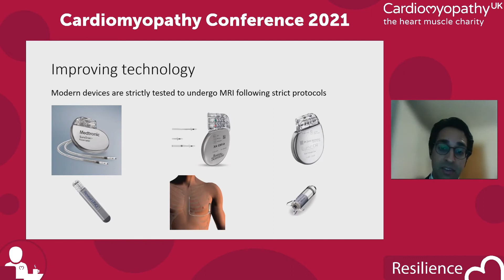And so these modern devices now come in all sorts of varieties. So all the devices I've talked you through earlier are available in MR conditional models from different manufacturers. And that includes the leadless pacemakers and the subcutaneous devices. And the technology that's gone into them is really remarkable. And we know that they can undergo MRI very safely. There's a lot of data to date about that now. But one has to take those steps to make sure that they can be done by tweaking the MRI scanner and tweaking the device itself.